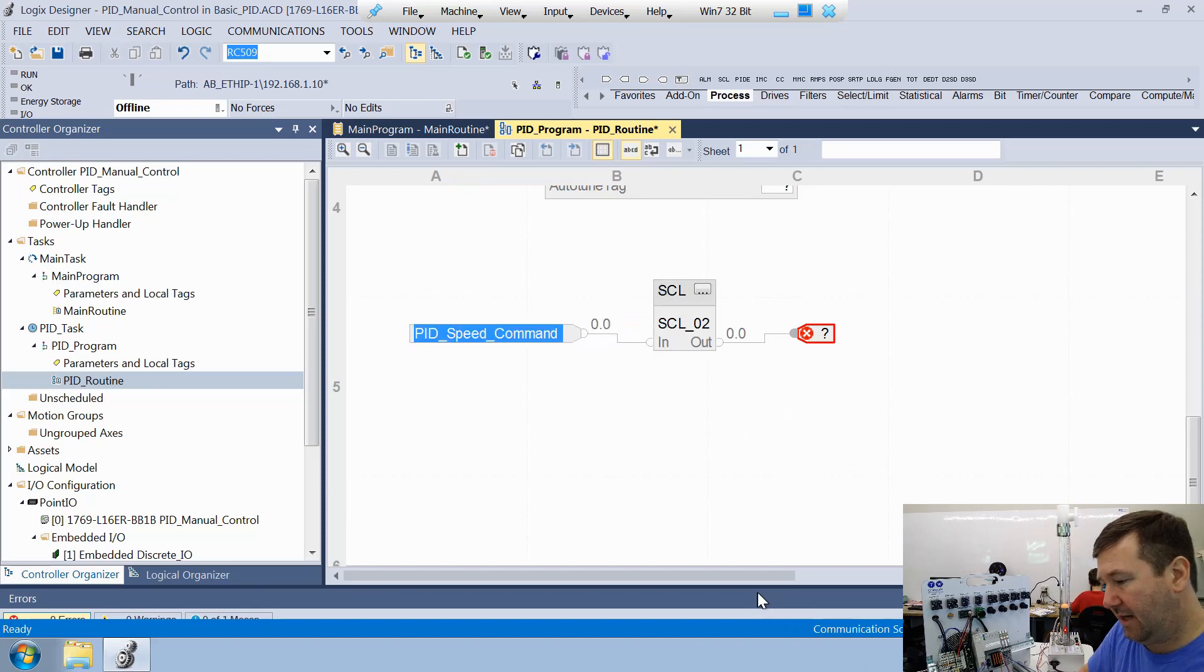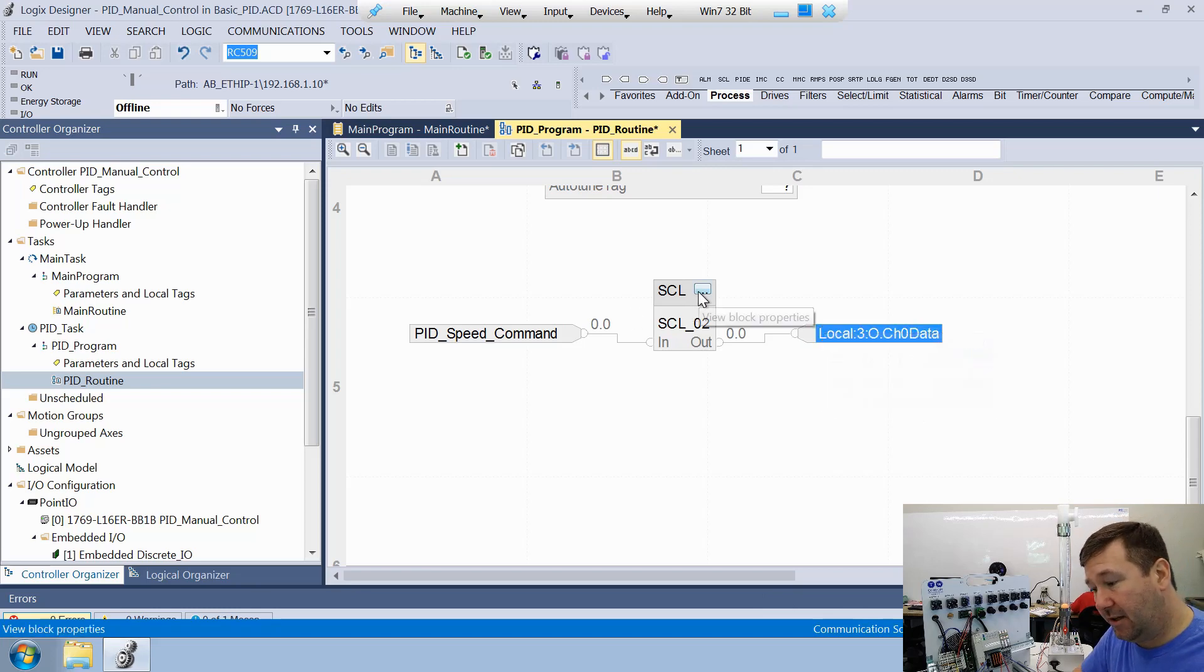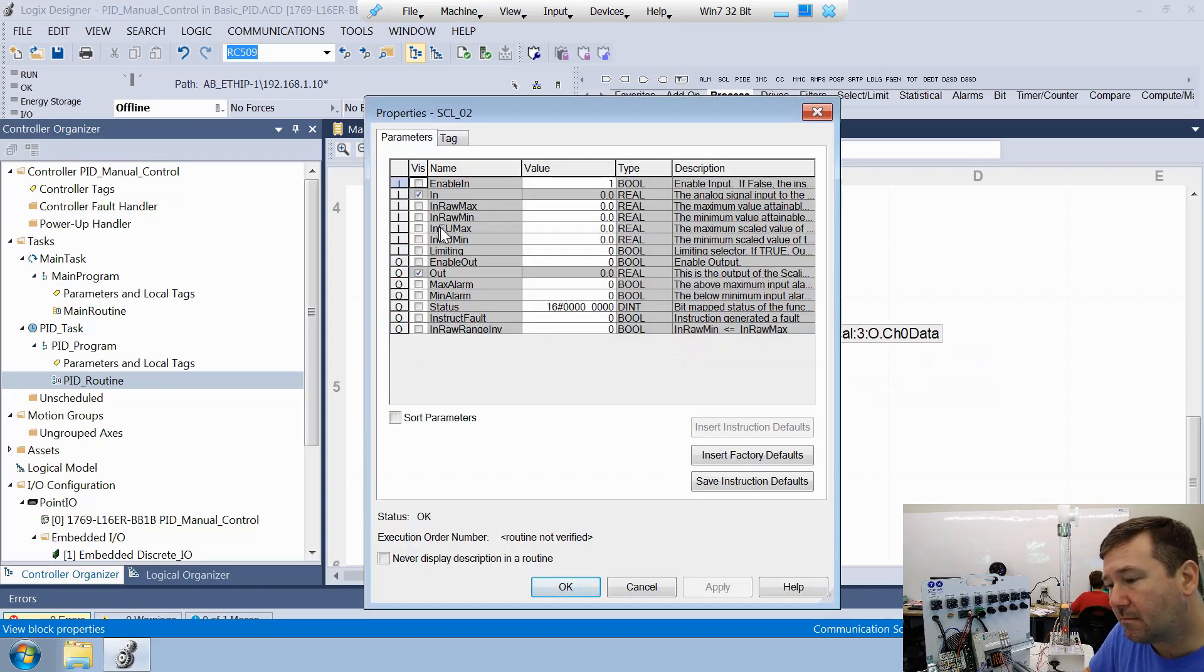So PID speed command, and then our output is going to be local colon three colon O dot channel zero data. And then we're going to need to configure this block. So we'll click the view block properties and our PID right now is set up for zero to 100%. So that's going to be our raw minimum max is zero to 100. And then our engineering units for our analog output are zero to 10,000 equals zero to 10 volts. So engineering units max will need to be changed to 10,000.